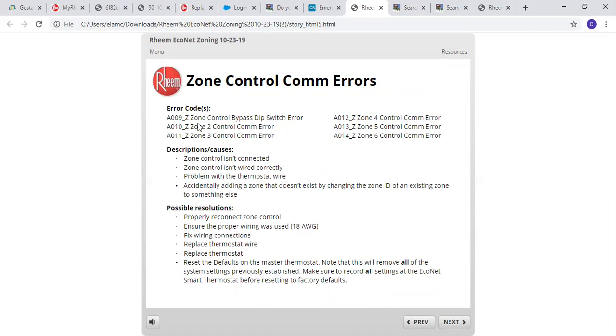Zone control communication error. Depending on which one you're looking at here, if your third zone has a communication error, A011Z, zone 3 communication error, could be 4, 5, and 6. Some possible causes: zone control isn't connected. Zone control isn't wired correctly. So if you cross up your E1 and E2, that will certainly cause a communication error. If you have a problem with your thermostat wire, or accidentally add a zone that does not exist by changing the ID of an existing zone to something else, that can also initiate a communication error.